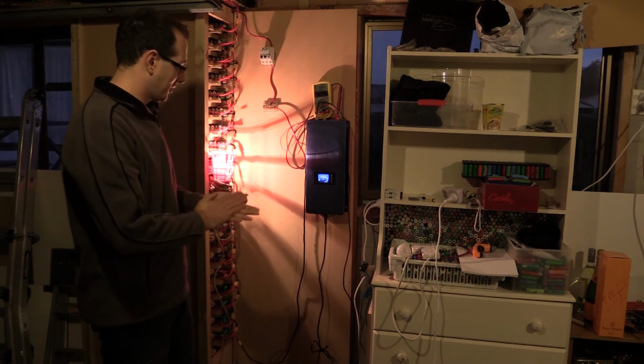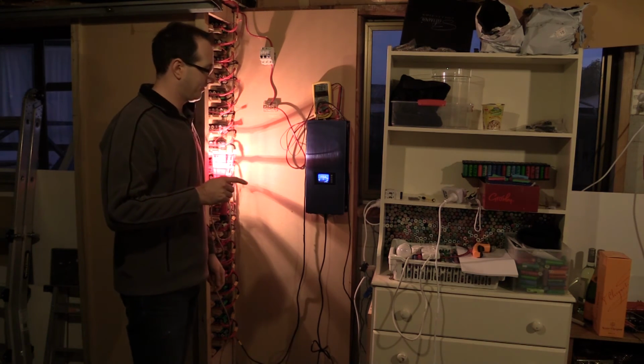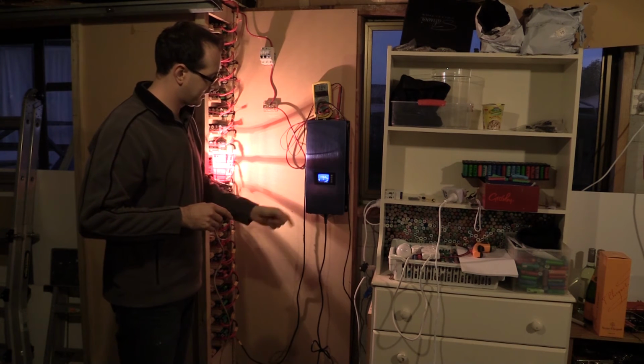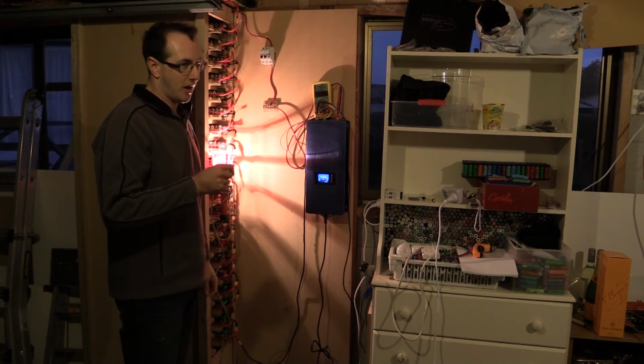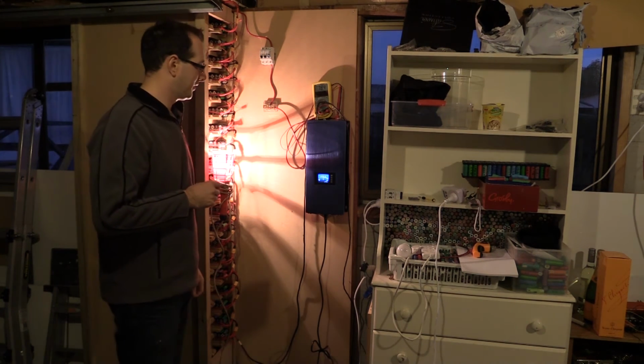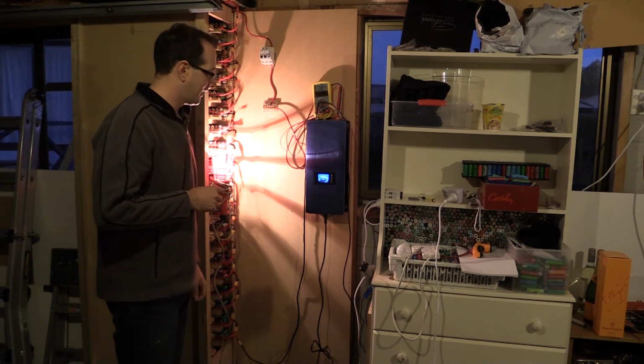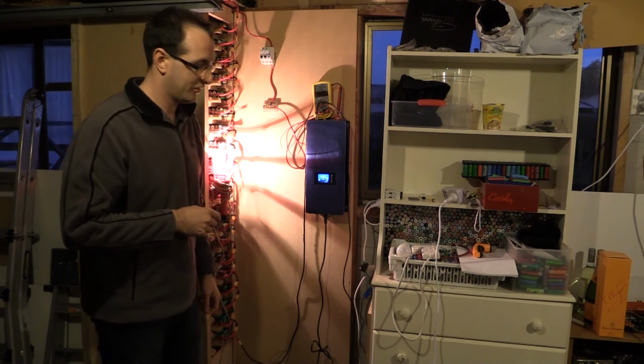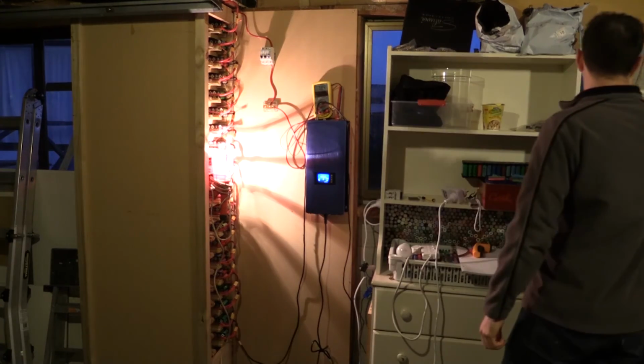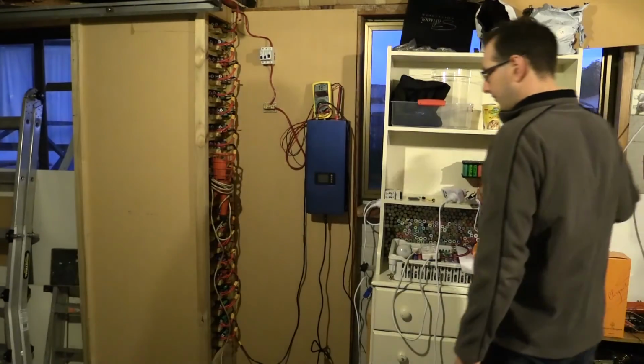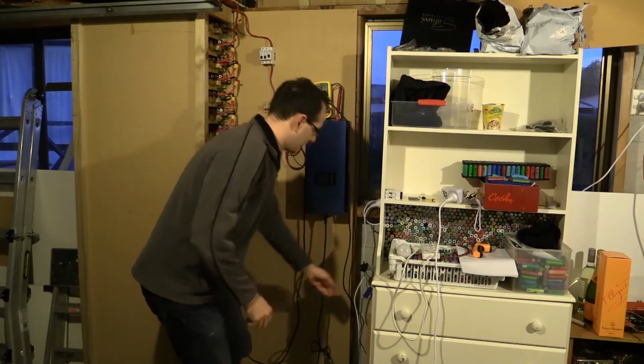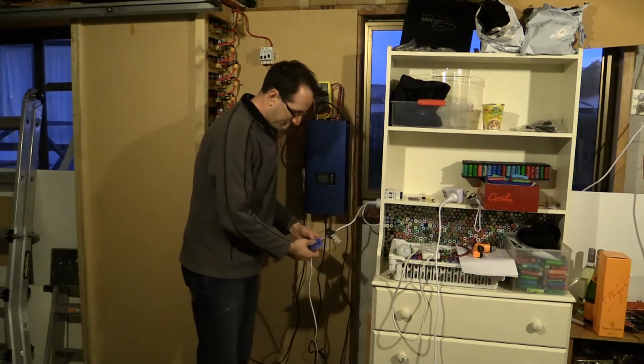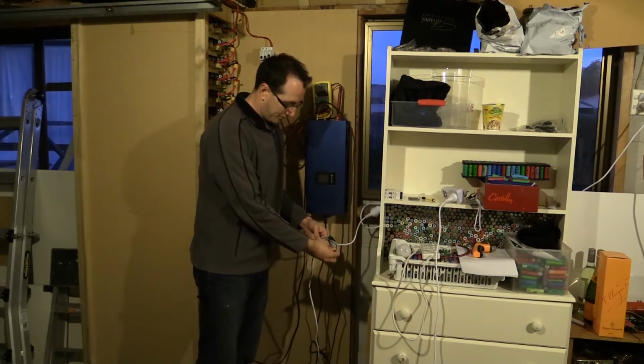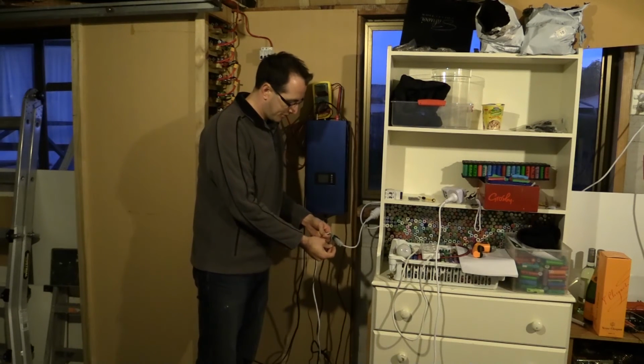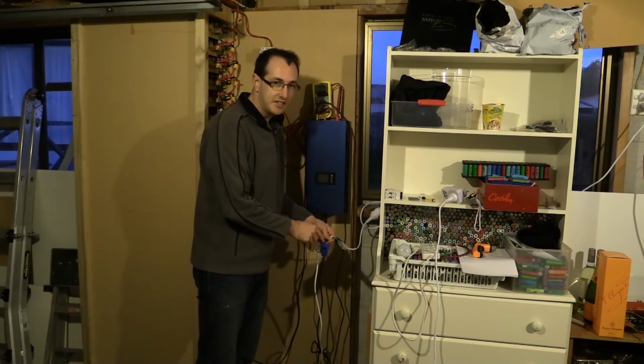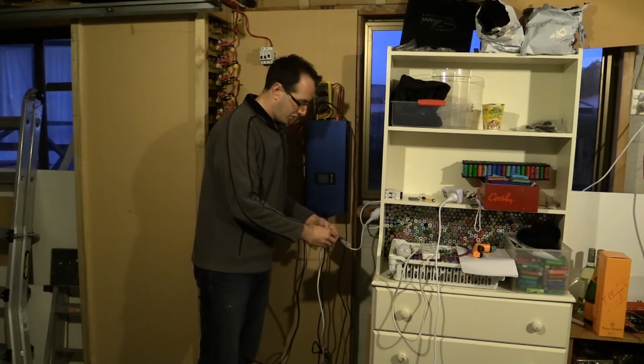Happy with that. What I'll do now is I'll just quickly turn the inverter off. I'll just unplug this, unwind this extra cable that's around the CT clamp, and then we'll get a better reading of what we're actually seeing. So just 2 seconds while I do that. So what I mean by that is this cable here, so I've got a single 240 volt cable that comes out and around the CT clamp twice. So it only should go around once.